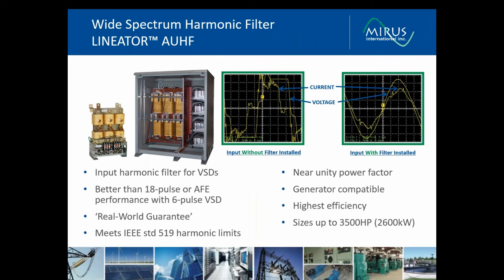So now let's talk a little bit about a passive solution, a wide-spectrum harmonic filter. This is our lineator, MIRUS' lineator filter. It's an input filter, treats harmonics generated by the variable speed drives. It's a simple passive device. Outperforms multi-pulse drive systems, active front-end drives, and active harmonic filters. When you consider all of the conditions for multi-pulse systems, we've got the voltage imbalance, current imbalance problem for active front-end and active harmonic filters. We've got the high-frequency noise problems. When those are all factored in, the lineator outperforms them.